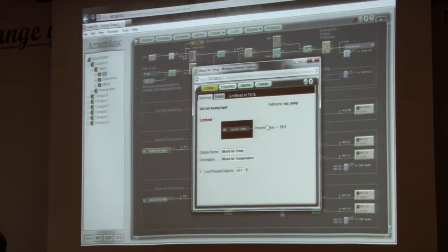Now you picked fire systems, and out of everything else, there's one thing to remember about fire systems. We can't write to a fire system, and they will cut off our communication if they have to, because the fire system has to be able to do its thing. So we can't send it anything, we can't tell it anything, we can just listen to it, because we can't interrupt the fire system. But we're always hoping to hear from the fire system, which they test, and they want to make sure, because they're going to say, well, if this fire alarm point goes off on the second floor, then we want all the exhaust fans for the second floor on, but then we want the first and the third floor to start overpressurizing, push all that smoke in the fire to keep it on the second floor, so that's what they want to test.